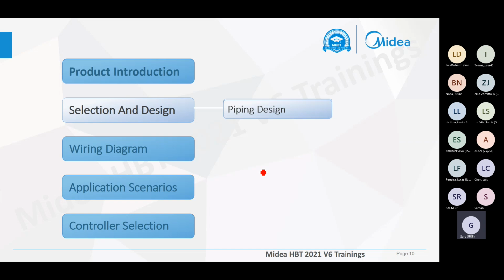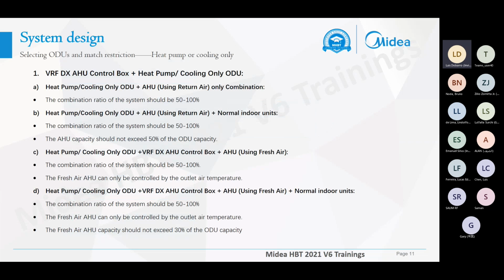And the second part is the selection and the design. Firstly, we should know some rules of the VRF systems when they connect to the AHU kit. Firstly, we will cover the heat pump and cooling only units. First, when the AHU kit connects directly to the VRF outdoor unit, and this system only has AHUs, the maximum combination ratio is 100%, and the minimum capacity ratio should be 50%.